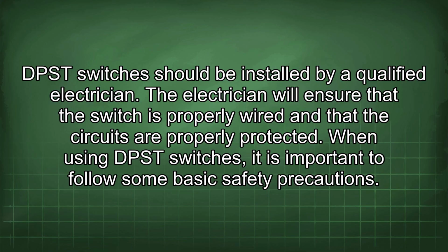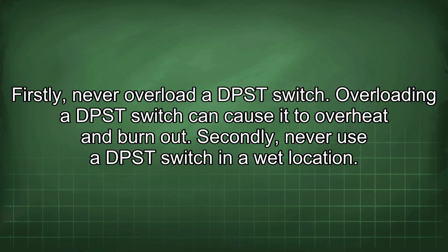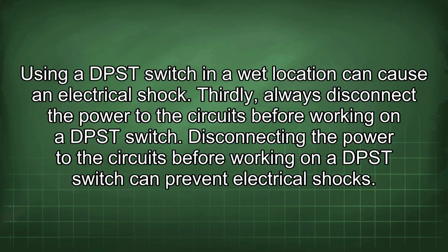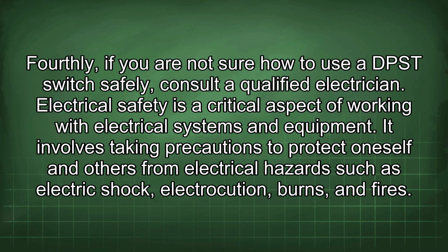When using DPST switches, it is important to follow some basic safety precautions. Firstly, never overload a DPST switch. Overloading a DPST switch can cause it to overheat and burn out. Secondly, never use a DPST switch in a wet location. Using a DPST switch in a wet location can cause an electrical shock. Thirdly, always disconnect the power to the circuits before working on a DPST switch. Disconnecting the power to the circuits before working on a DPST switch can prevent electrical shocks. Fourthly, if you are not sure how to use a DPST switch safely, consult a qualified electrician.